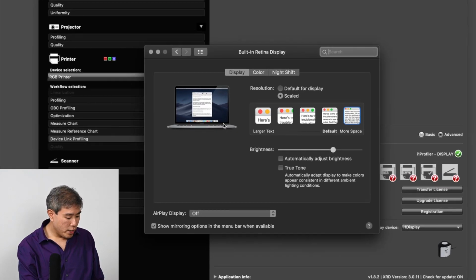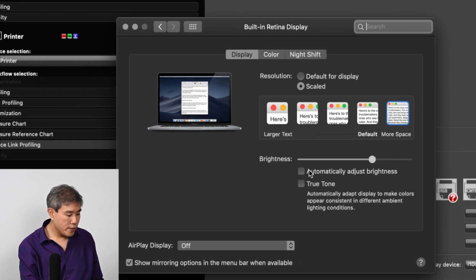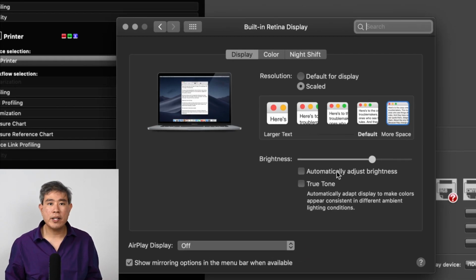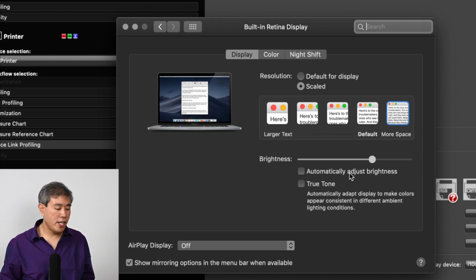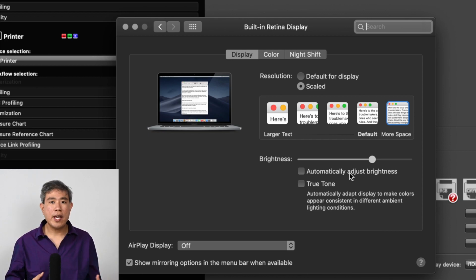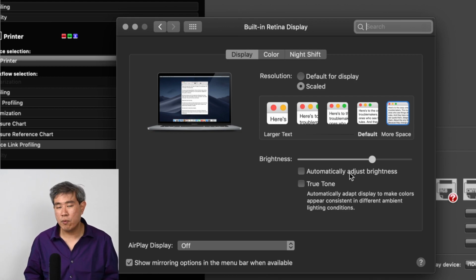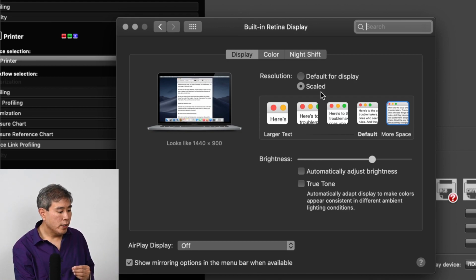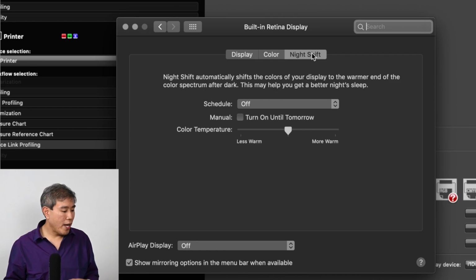And the one thing we're going to make sure is disabled in this case is the automatically adjust brightness. If you don't have that disabled, what's going to happen is that as you take your laptop to different environments, your laptop screen is going to constantly adjust to those environments. And in that case, you won't have the proper luminance value. So you want to disable that. Secondly, most Macs now have a Night Shift mode, and you also want to disable Night Shift. This way your laptop screen doesn't turn warmer or cooler at certain set times of day.